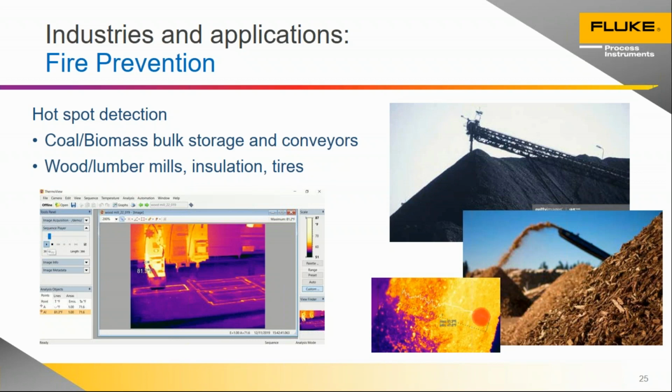And this hopper was a big, dark room where you couldn't really see anything looking into there, but with the thermal imager, you get a much different view. You have a distinct difference in temperature between some of the chips coming in and the others, and you could really easily catch a hotspot before it develops into something dangerous.